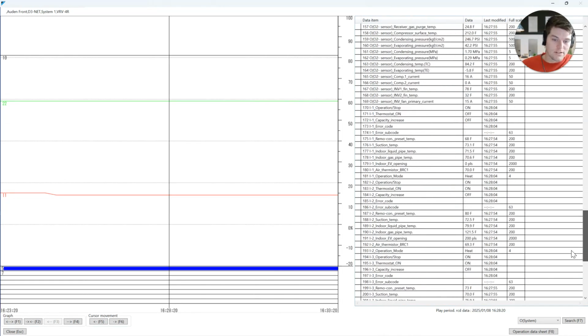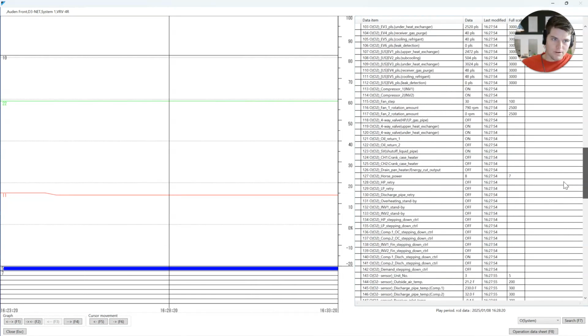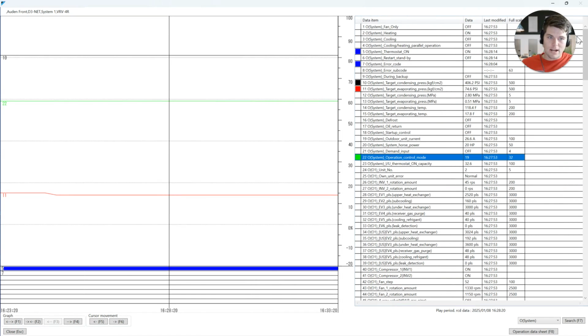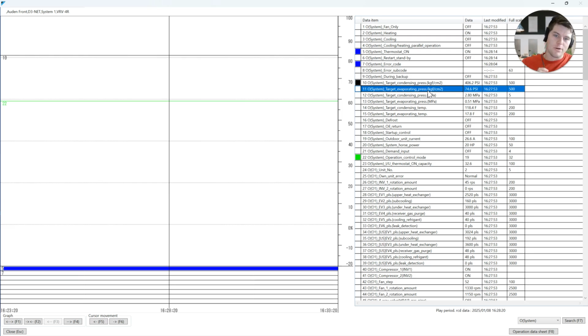Today's main focus is going to be on the three pillars, mainly discharge superheat, and I'm going to show you why it matters, why it's important, what it is, how we find it, all the little tiny tidbits. I'm going to blow some minds. So operation control mode. What do I know about heating mode? I don't need to look at my target evaporating pressure. If anybody has told you that it uses both at any given time, they have no idea what they're doing. You should run in the opposite direction. In heating mode, we are looking at target condensing pressure. In cooling mode, we are looking at target evaporating pressure.